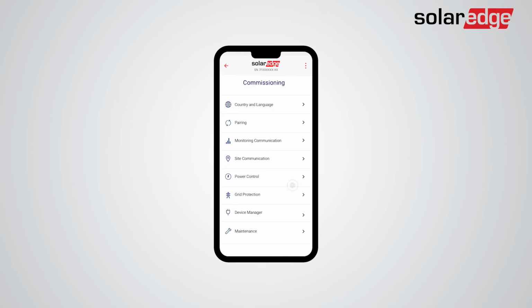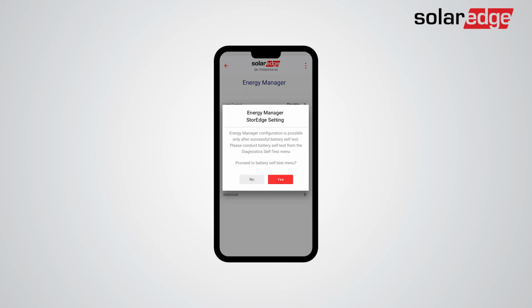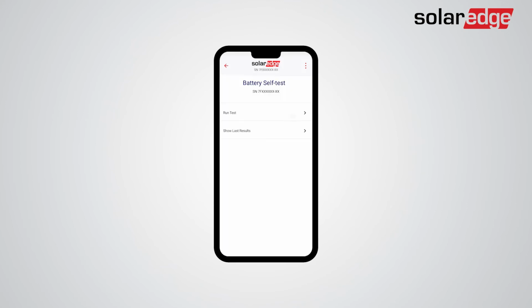Tap Power Control. Tap Energy Manager. Tap Energy Control. Now, you will be prompted to conduct a battery self-test. Tap Yes. Then tap Run Test. The battery self-test should take approximately 1 minute per battery.